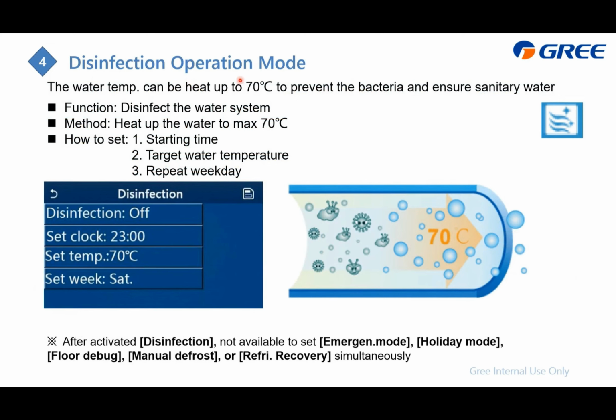Disinfection operation mode. The purpose of this one is just to heat up the DHW to a high temperature to make the system clean. And what you can set is whether you need this function or not, when to start it, and which temperature. The max is 70, and when to do it again.